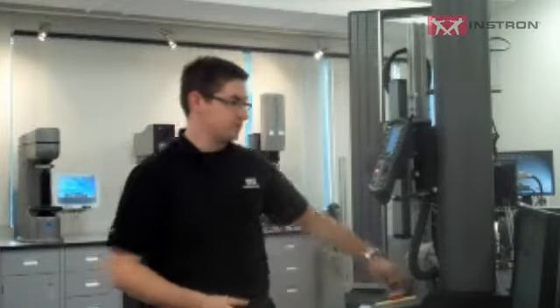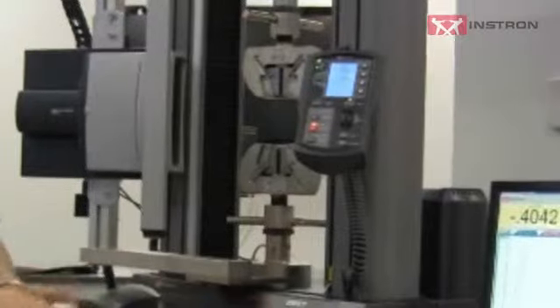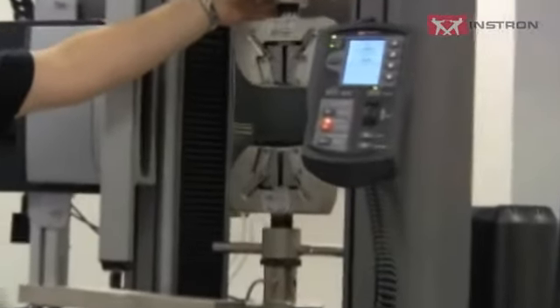In this case, we have a set of mechanical wedge grips. The faces actually move during testing, so we want to make sure that the compliance is completely taken off.